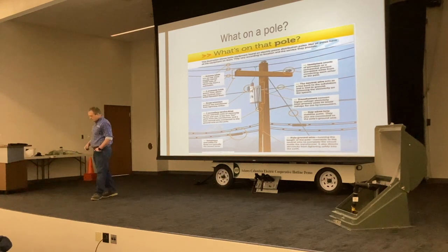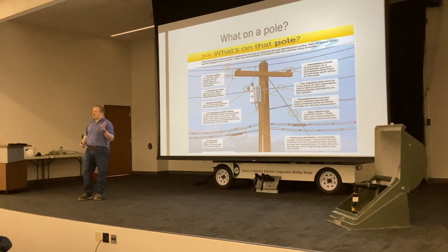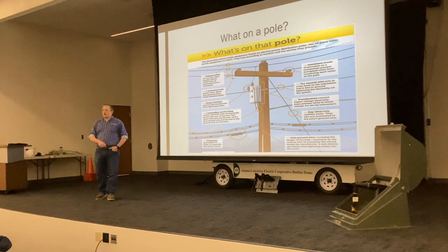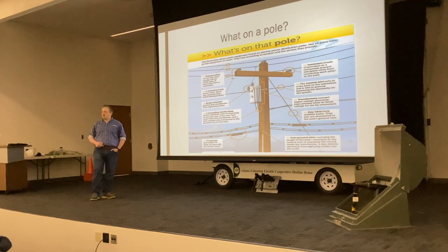So these guy wires, what I want you to remember, because they have no stretch, they have no give, they come all the way down to the ground. If you had something pulled really tight, and then you cut one side, what do you think is going to happen to that other side? It's going to whiplash, it's going to have huge counteraction. What can happen if that guy wire gets broken at the bottom, say a snowplow hits it, machinery hits it, even if it rots away, or farm equipment hits it, is that pole will see a massive shake, and you can actually have that pole break off in more than one spot. We got some photos of that later on.